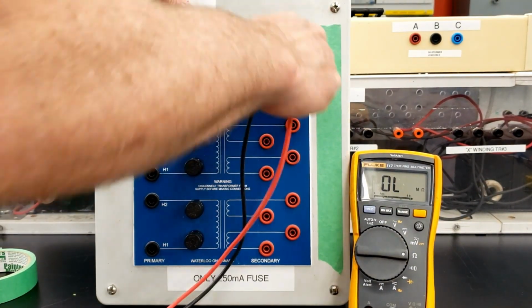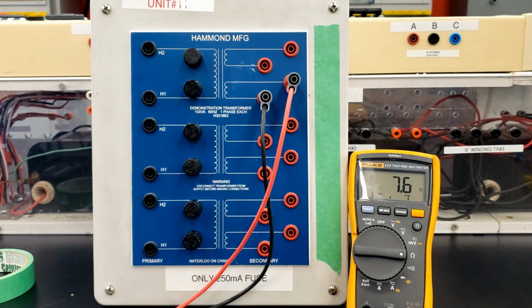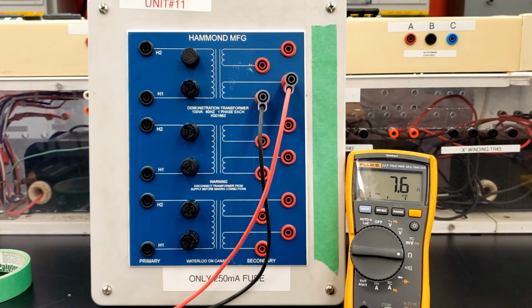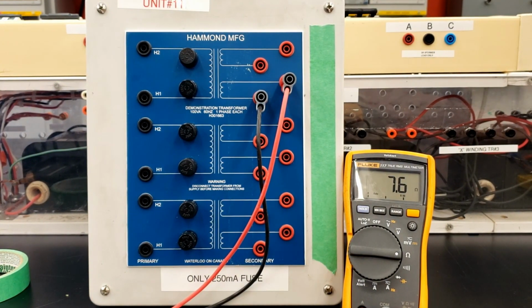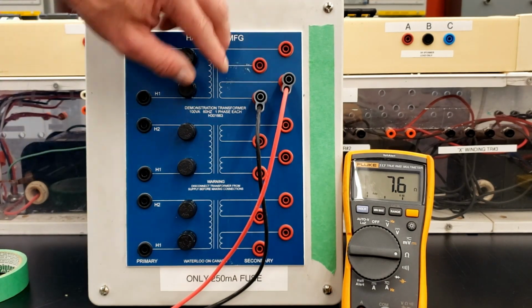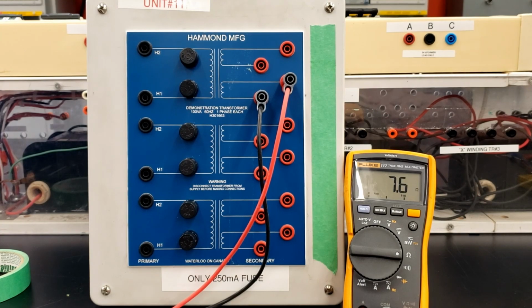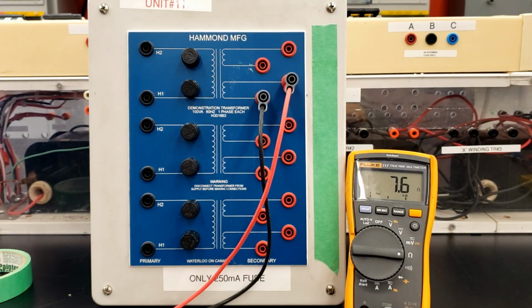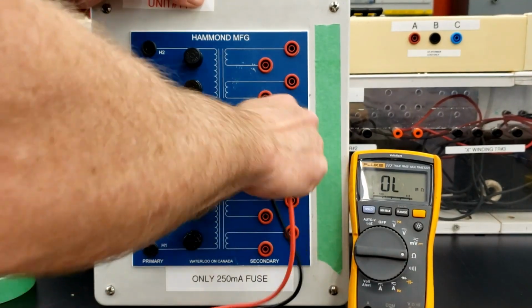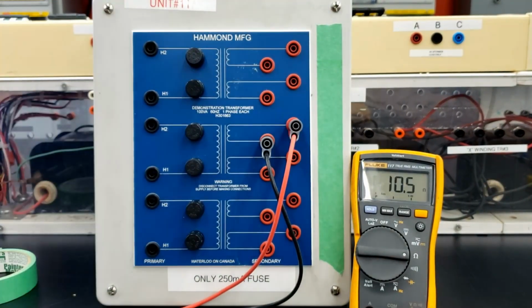Let's see whether that winding is smoked compared to the others, meaning it has a higher resistance. Okay, that's 7.6. You can see these transformers have been beat up quite a bit. We'd like to have the same resistance value on all of them, but previous students have shorted out the secondaries, affecting the resistance of the windings.